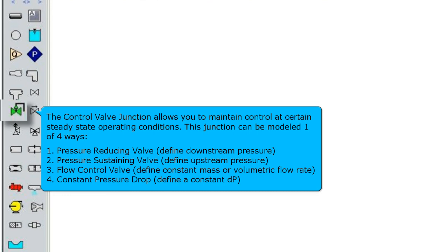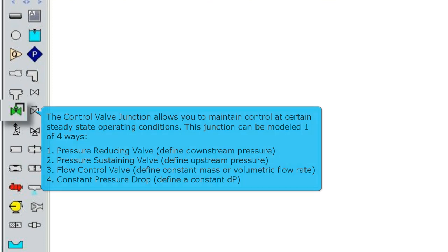A pressure reducing valve by defining downstream pressure, a pressure sustaining valve by defining upstream pressure, a flow control valve by defining constant mass or volumetric flow rate, and a constant pressure drop valve which maintains a constant pressure drop regardless of the flow.